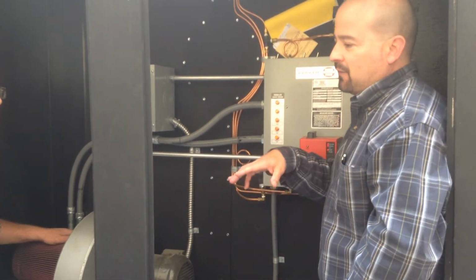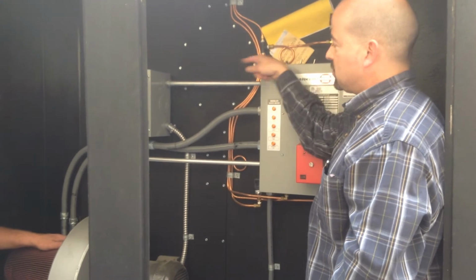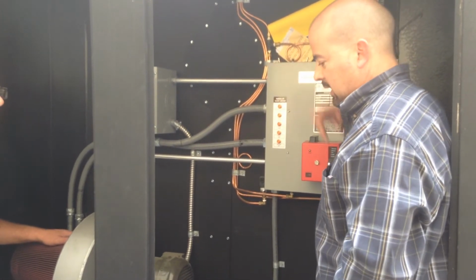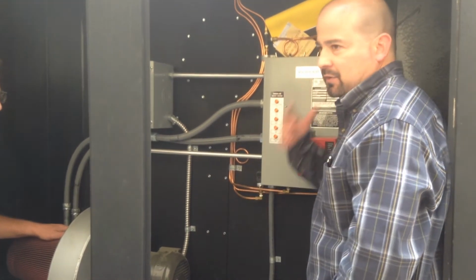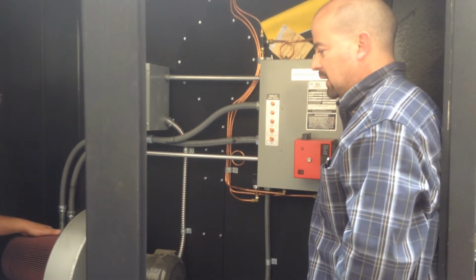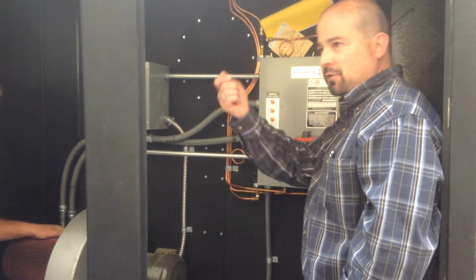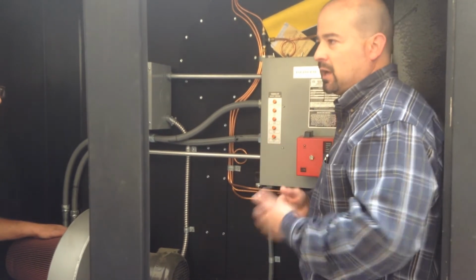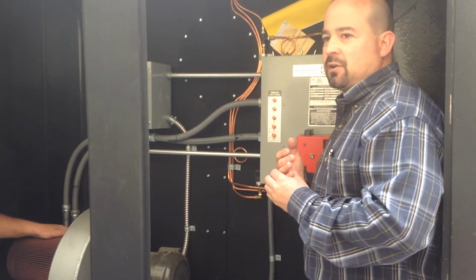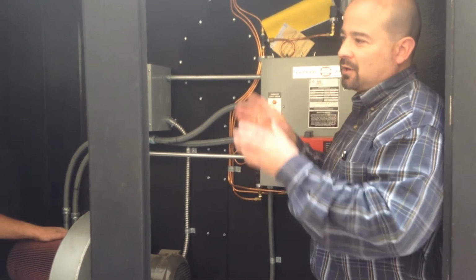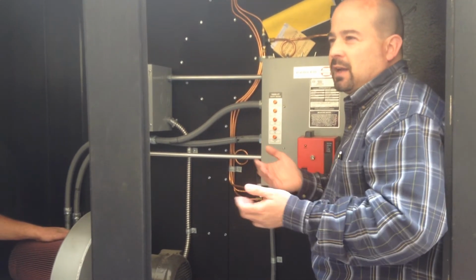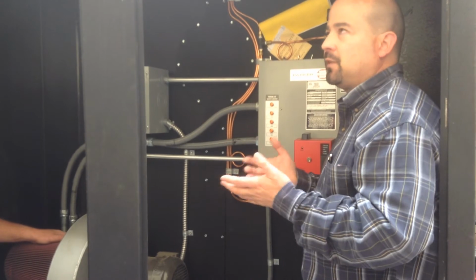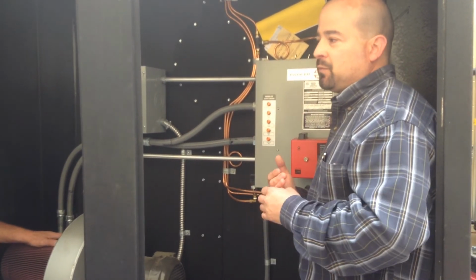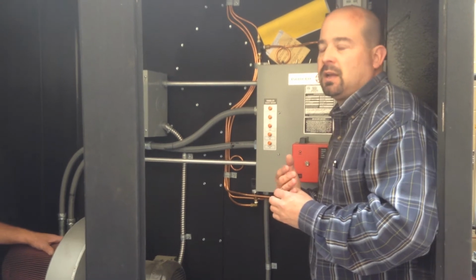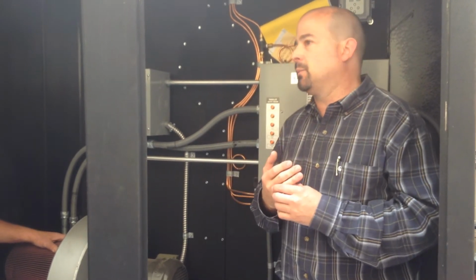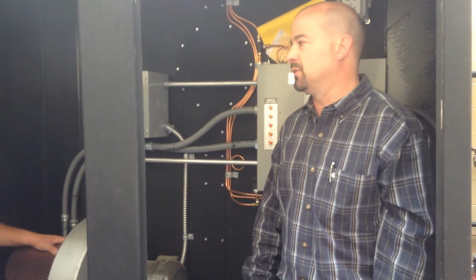If you're going to shut the boiler off for the season, go ahead and turn off the control switch, that one there, and then I would go ahead and isolate the natural gas, maybe lock it out for the season, that's fine. The deaerator, it's pretty self-explanatory, just turn everything to off and manually turn off all your isolation valves. Whether you want to drain it or not, draining it probably would be a good idea because you're going to have chemicals going into there. Yeah, you'll have sulfites, which are kind of aggressive. Sulfites aren't as aggressive as the phosphates that are going in the boiler, but depending on the layup time, how long you're going to be, you may want to drain it down. Phosphate sitting in a boiler for a long time is probably not good. You probably want to drain the boiler down for your summer season.